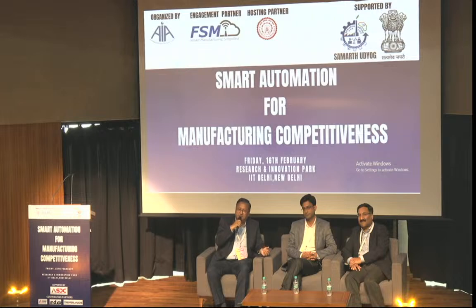But sir, many times these acceleration sensors are not enough. Where there are heavy machineries with gears, they normally break, like turbo machineries, because of torsional vibration. So it comes with experience, as you rightly said. With a big motor, say a huge induction motor, maybe one axis is not enough. You have to use multiple sensors at 2 or 3 different locations. That's the way to do it. Thank you very much, sir.